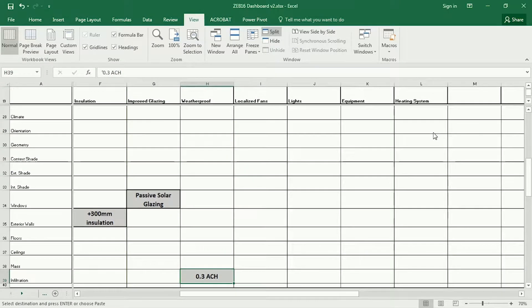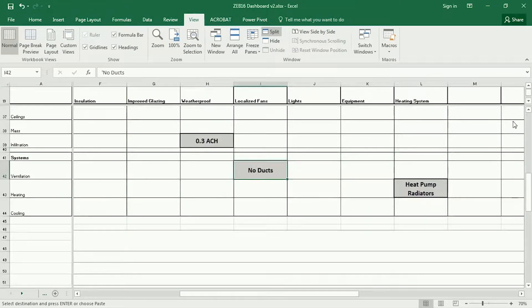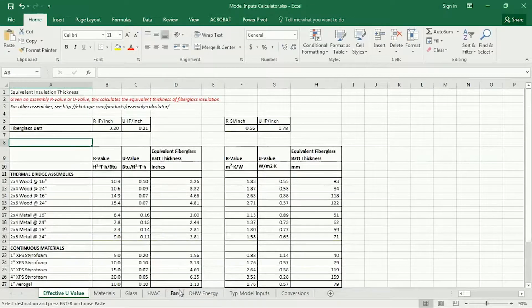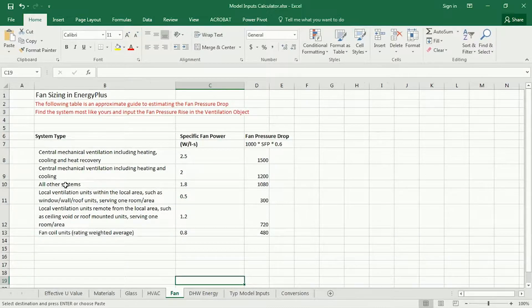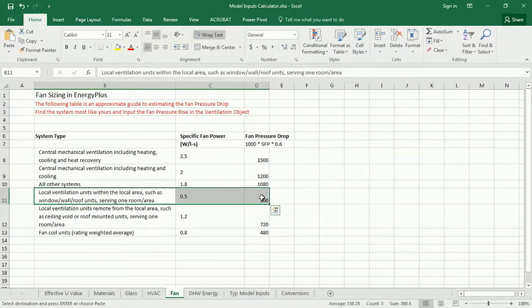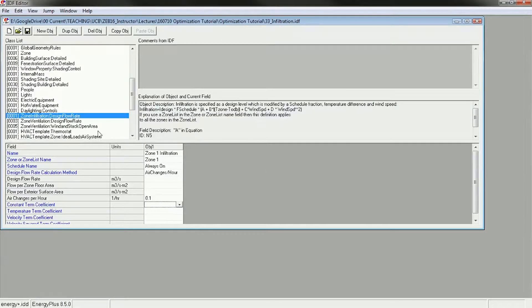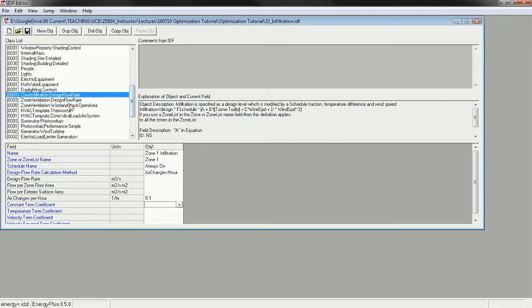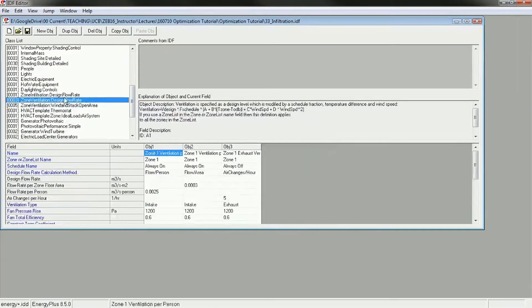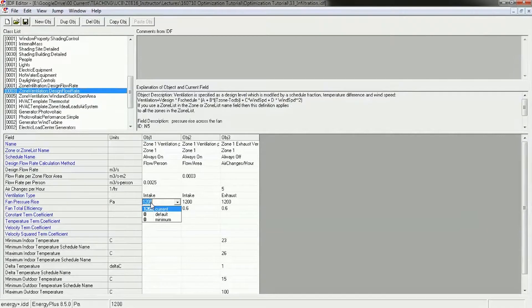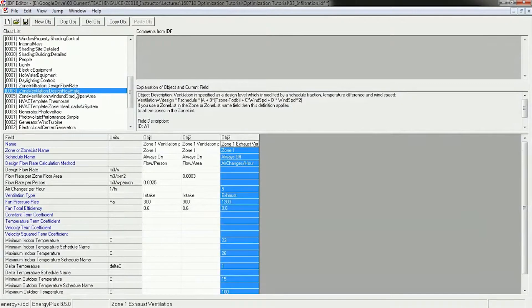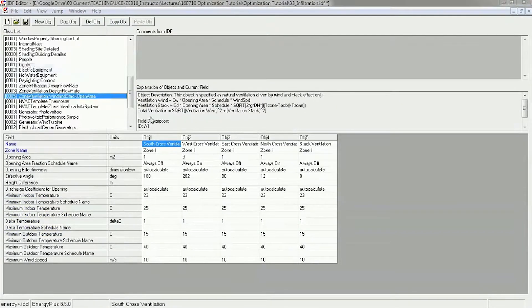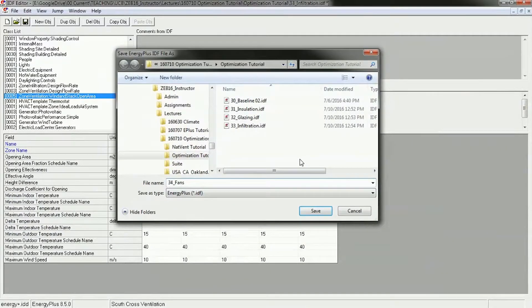The next one is localized fans. So I'm going to use no ducts. And if I go to the model inputs calculator, I can go to the fan tab and see that the fan pressure drop for localized ventilation units is 300 pascals. And in EnergyPlus, I can go to my fan and change it to 300 pascals here and here. I'm not using this fan, so I'm not going to bother to change it. I'm going to save this as 34 fans.